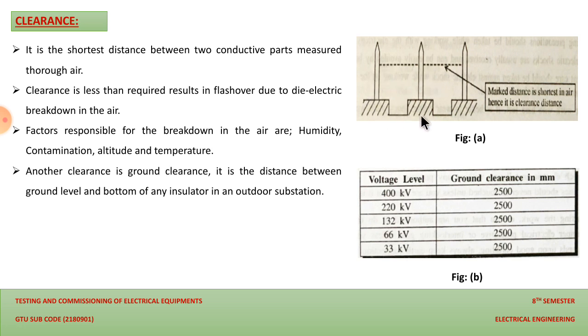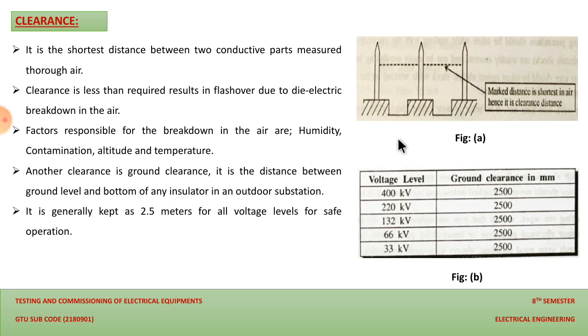So yes, it is the distance between two consecutive electrodes, and we can say grounded distance means where they are grounded from one point to another point, so it is called the grounding distance. So yes, it is again necessary for an outdoor substation. And it is generally kept at 2.5 meters for all the voltage levels. So over here you can see these are the voltage levels, and this is the ground clearance in mm. So from 33 kV to 400 kV we are keeping a distance of 2500 mm or 2.5 meters. So this is the standard distance.